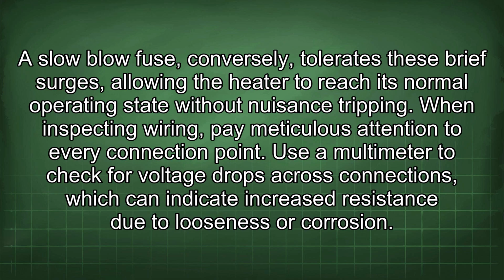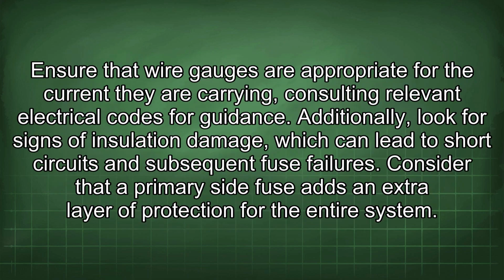When inspecting wiring, pay meticulous attention to every connection point. Use a multimeter to check for voltage drops across connections, which can indicate increased resistance due to looseness or corrosion. Ensure that wire gauges are appropriate for the current they are carrying, consulting relevant electrical codes for guidance. Additionally, look for signs of insulation damage, which can lead to short circuits and subsequent fuse failures.